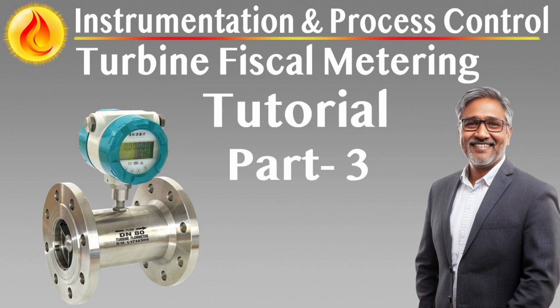Each metering run must include a dedicated flow control valve to regulate the flow rate through the turbine meter and enable stable conditions during proving, turn down, and transitions between meter runs. These valves are typically pneumatically actuated for precise responsive control and must include a side-mounted, declutchable handwheel for manual override in case of actuator or air system failure.